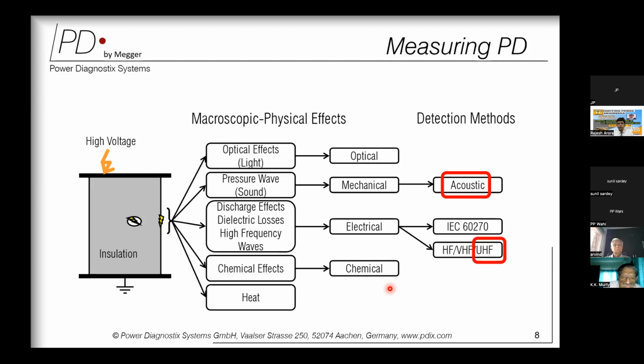However, the electrical UHF measurement method, UHF meaning ultra high frequency, is the most reliable method which can be used to detect each and every type of partial discharge defect happening due to various reasons. And this is universally accepted. The UHF measurement method is universally accepted as the right method to do the partial discharge measurement in GIS.